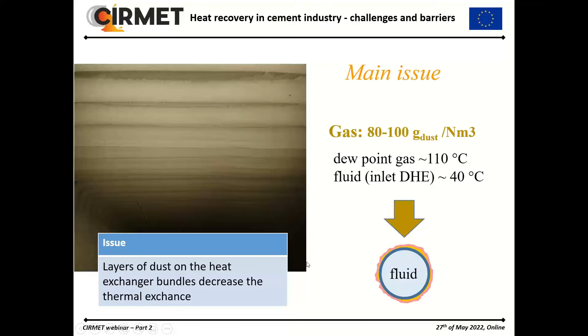We try to solve this problem by performing periodic cleaning of the heat exchanger, increasing the frequency of the cleaning system, which in Piacenza is a hammering system, and preheating the direct heat exchanger in the starting phase before the gas inlet.